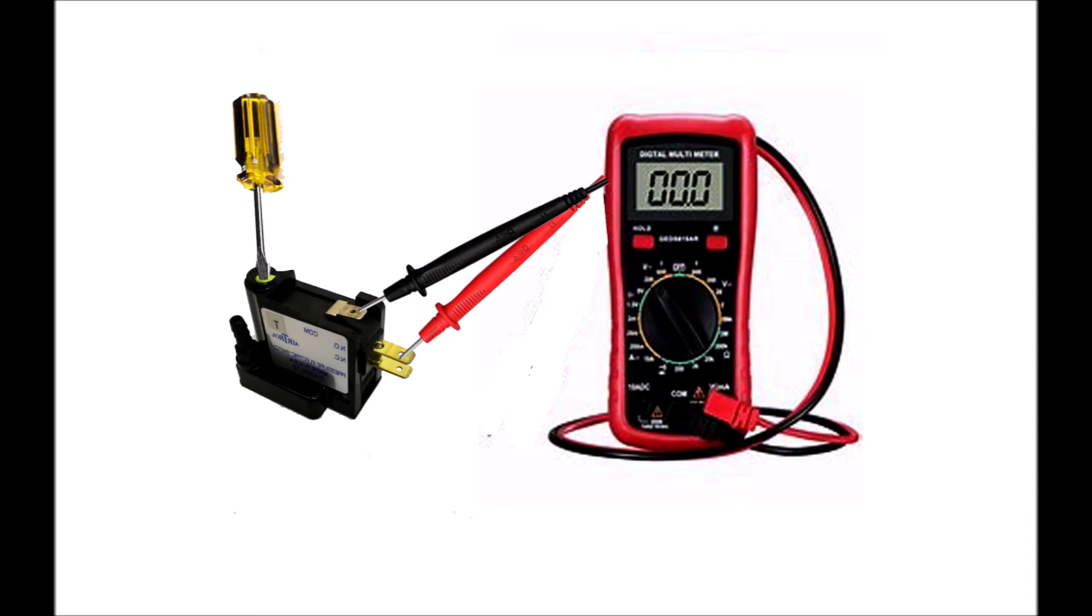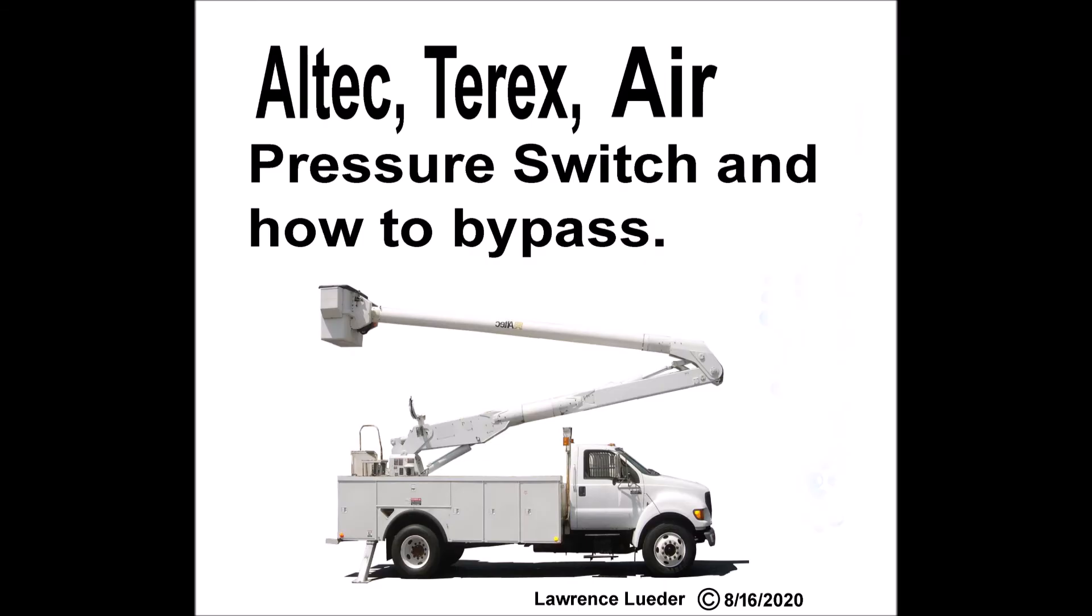Again, this guy was wrong, because when you turn in the screw it increases the air pressure required to make the contact. If anything, you turn the screw out, which reduces the amount of air pressure required to make the switch click.